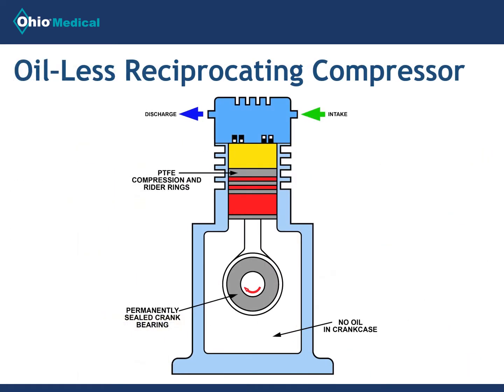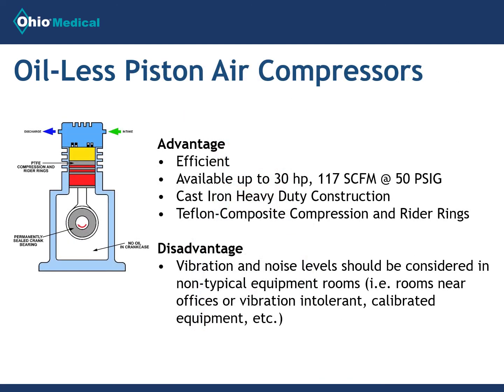We also offer oilless piston compressors, both in our complete systems, as well as replacements for existing piston compressors in hospitals and labs. These replace Quincy, Ingersoll-Rand, PowerX, and Champion models. These piston compressors are available in sizes from 3 to 30 horsepower, which makes them ideal for facilities with high capacity requirements. One of the advantages of oilless piston compressors is that they usually produce higher CFM per horsepower than scroll compressors, and their cast iron construction assures long-term durability.